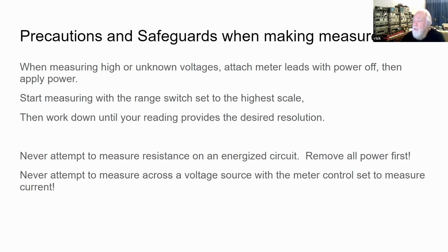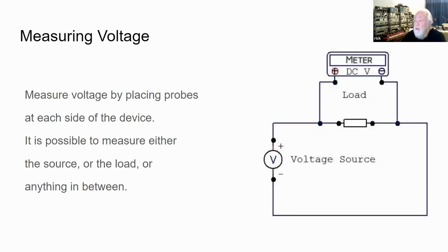You never want to attempt to measure resistance on an energized circuit because you could damage the meter or the device you're measuring and you won't get a valid reading. And of course, never measure across a voltage source with the meter in the current position. And once we discuss how meters work internally, you'll have a better understanding of why that is.